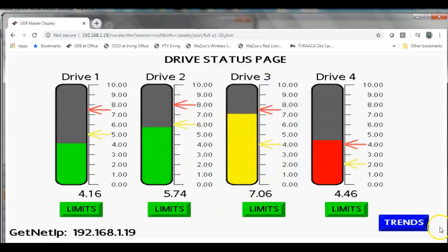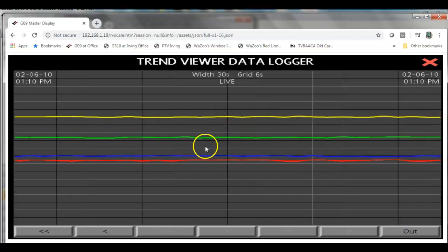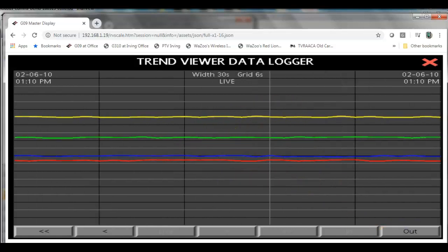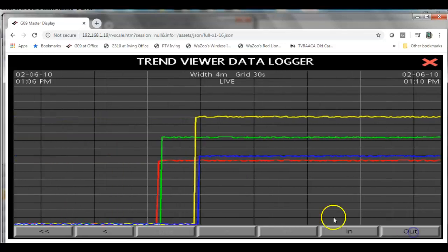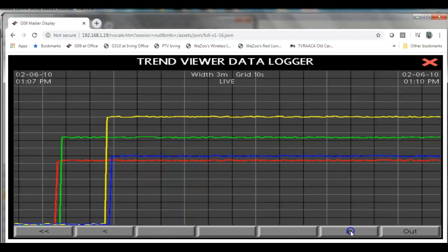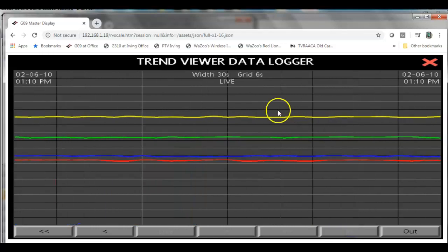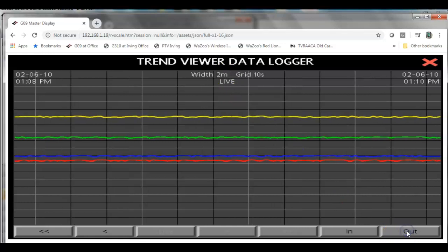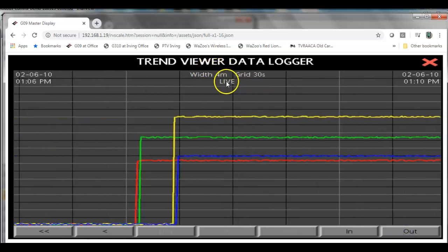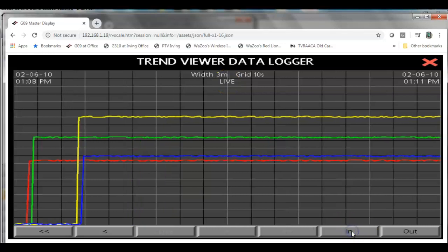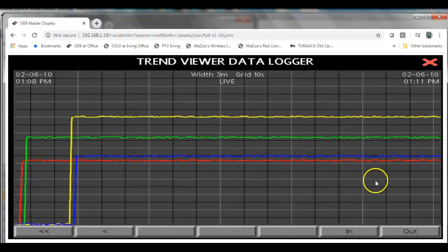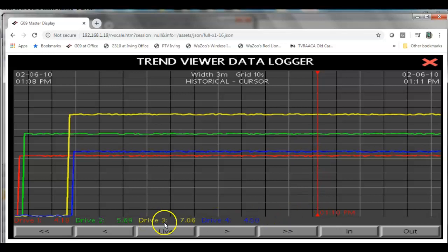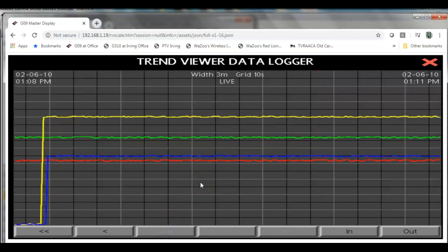One more thing I've done here. Besides this raw data, I'm also taking advantage of the data logger. If I click on the word trends over here on the left, I can actually look at a live trend view of those values. We can actually see when I turned it on and when I've been playing with the values here on this screen. You can go all the way down to a 30 second resolution, or you can tab all the way out to two days or 48 hours of continuous information. You can click anywhere on here, and at that moment of time, it'll show you what the values are.